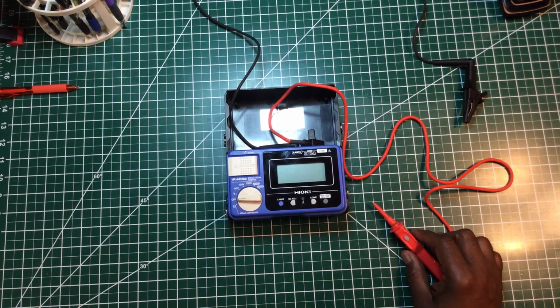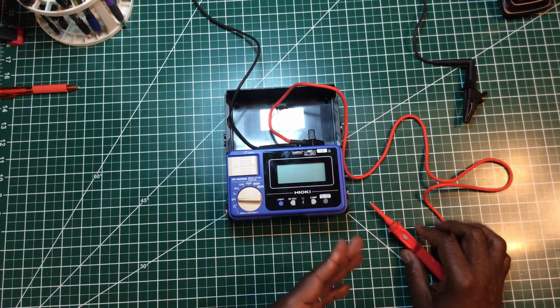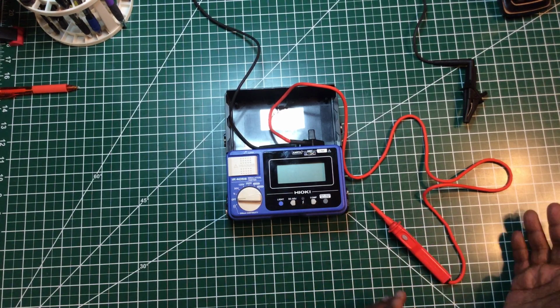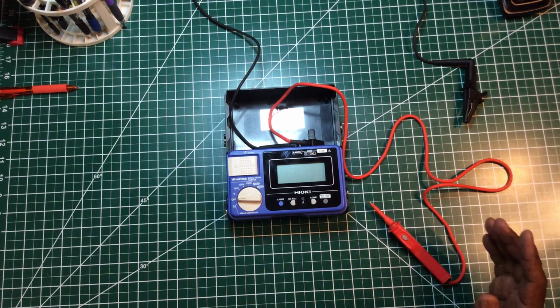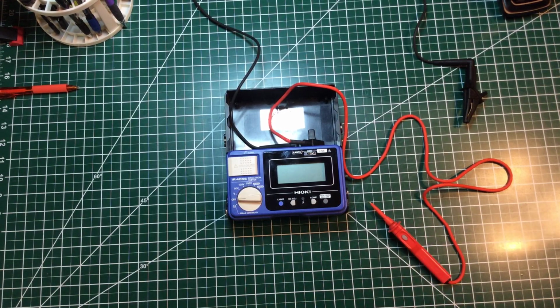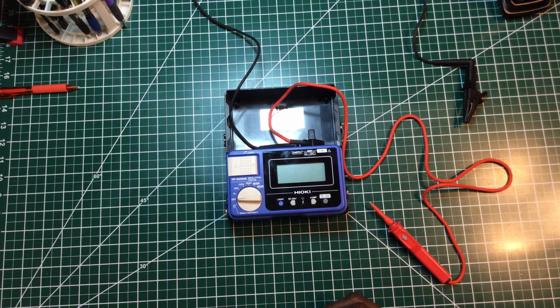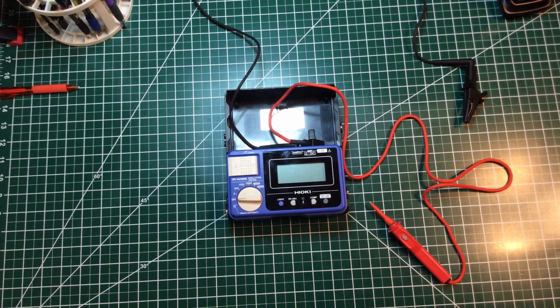all the time, and I used it when I'm doing residential, if I'm testing the integrity of a branch circuit or some old wires in the wall that I'm about to reconnect a new appliance to or whatever. I want to check and see if the integrity of that wire is good, and it will pass. So that's what I do - I'll just test it, and if it comes back good, well, okay, we could go with that. If not, I'll have to pull more wire.